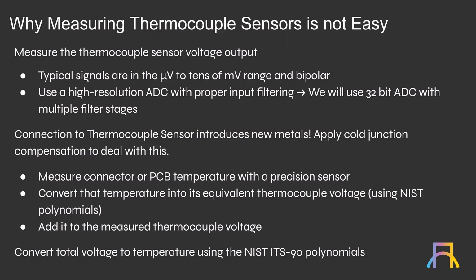Well, how do we deal with that? Well, we can apply cold junction compensation. The idea is, if we make a temperature measurement where this junction is, where the thermocouple metals that we know about are meeting the metals of our design, we can make a temperature measurement there locally and compensate for that in our code. And that's covered in our polynomials and in the ITS-90 approach, right? It's often referred to as cold junction compensation.